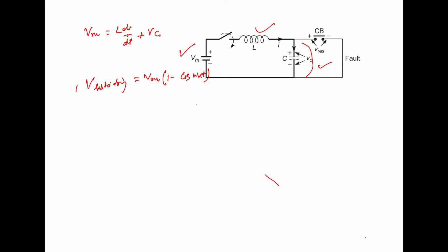Further, we have totally ignored the resistance of the system in this derivation. We have not assumed that resistance is there. So the restriking voltage appears to continue forever according to this equation. However, in the real system, the resistor is present, and the restriking transient will quickly die down, and the recovery voltage will be equal to the system voltage.